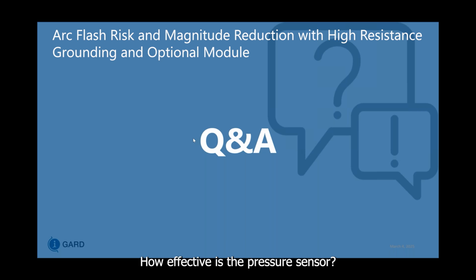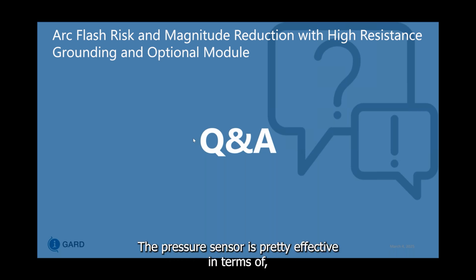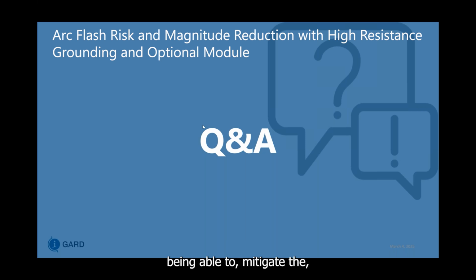How effective is the pressure sensor? The pressure sensor is pretty effective in terms of being able to mitigate the arc flash energy and being able to detect it. We've done a few internal tests where it's been quite as effective as the arc flash sensors, like the fiber optic ones. So it's been a valid way to mitigate arc flash energy.